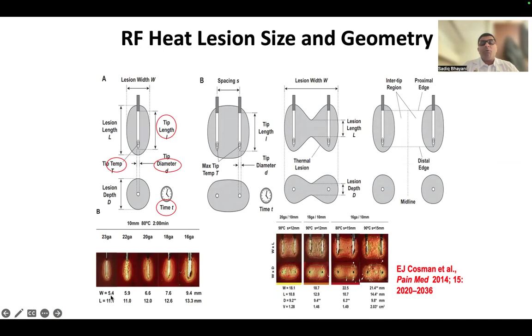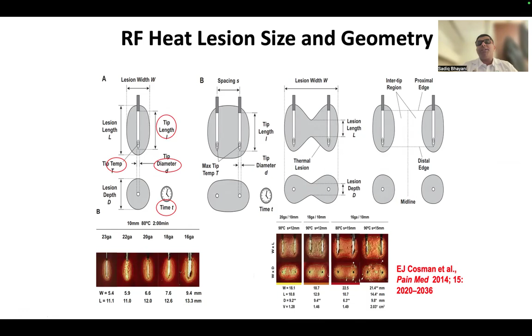And here we have a bipolar positioning of the needles. If you position the needles close to each other, you will get a good lesion. But if the needles are spaced away from each other by more than a centimeter, or 1.5 centimeters, then unfortunately you only get two individual lesions. So when you're performing radiofrequency, it's very important to consider which nerves you're targeting, what your needle size is, and what your exposed tip is. Is it 5 millimeter or 10 millimeter?